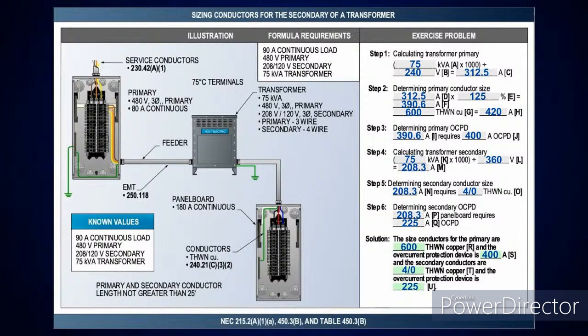Well, first thing I have to do, and we did this at the very, very start when we were doing formulas, and I was telling you how to get the amperage when you had the kVA rating there. Well, I've got 75 kVA times 1,000, and I'm going to divide it by 240 volts. That's going to give me 312.5 amps, and then I'm going to do the primary side conductor size here. So I'm going to take that at 125%, and that's going to give me 390.6 amps, which if I go over and look at table 310.16, the next size above that is 420 amps, which is a 600 kcmil conductor.